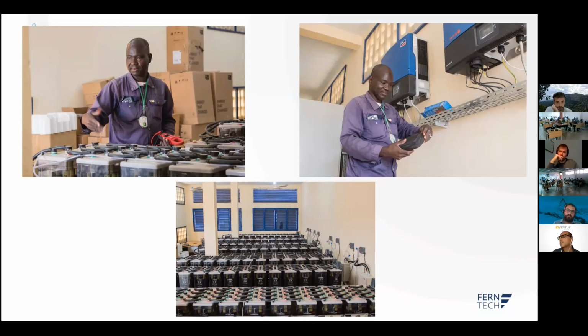So it's 772 kilowatt hour nominal capacity of the battery. Because it's a flooded lead acid battery, in order to have maximum lifetime you're going to be using half of it, so 50% depth of discharge. This leads us to 380 kilowatt hour usable energy. And if we take out inefficiencies from the battery, but also from the power conversion equipment, we end up with around 310 kilowatt hour usable energy.